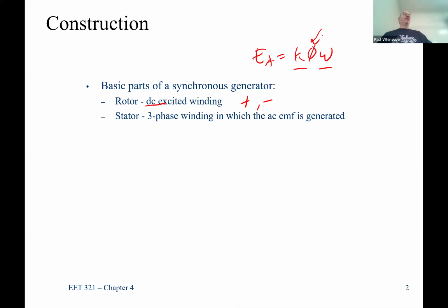The only thing we can adjust is phi, which is proportional to the magnetic flux in the machine. So we put more DC, which means it increases the flux. And that's how we can actually get control. So if our voltage is starting to get low on the terminals because of heavy load conditions, we just go ahead and put more magnetic field energy, which means we put more DC into the machine, and thereby the terminal voltage boosts up. The converse of that is if you've been running along heavily loaded, and then a big amount of load trips offline sort of instantaneously, then your excitation needs to be adjusted down because you don't want the voltage on the terminals to be too high.